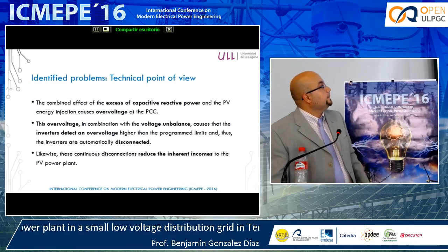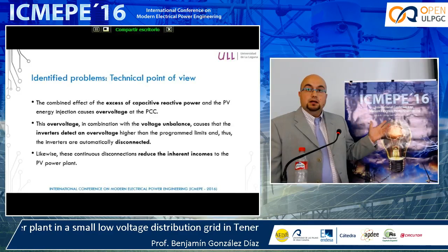So, thinking about that, together with our colleagues from the University of Las Palmas de Gran Canaria, and also with Endesa, the electrical company, we saw that the combined effect of the excess of capacitive reactive power and the PV energy injection caused the overvoltage of the line. This overvoltage, in combination with the voltage imbalance, caused the inverters to disconnect completely from the system, and it implies an economic loss. Likewise, this continuous disconnection, of course, reduces the income.